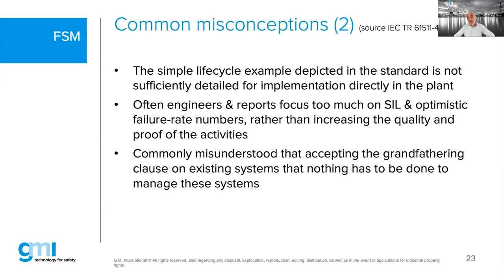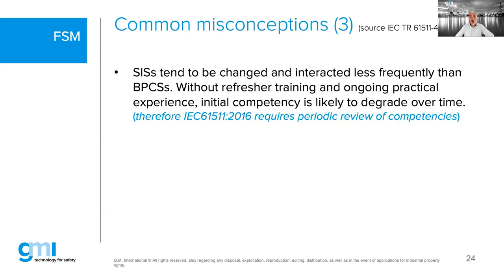Do you really believe it makes sense to predict with a SIL number precisely the availability of a valve where you even have no clue on the mission time, useful lifetime, and also have no clue on failure data? Take my word for that. You're wasting your time and you would waste certainly my time if I would make an assessment. So those are typical items that people totally forget when they are looking at older installations.